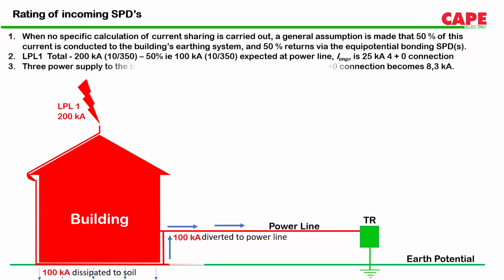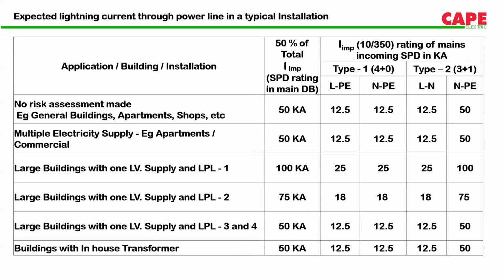Because we have somewhat lesser time, I'll just jump to the chart. Okay, so this is the chart. There are four lightning protection levels: 1, 2, 3 and 4. Level 1 has a maximum lightning current of 200 kiloamperes, whereas level 3 and level 4 have a lightning current of around 100 kiloamperes. In this 200 kiloamperes, 50% of the lightning energy comes back into our building. That means 100 kiloampere. Whereas in level 3 and level 4, we expect around 50 kiloampere of lightning current to come into our building.